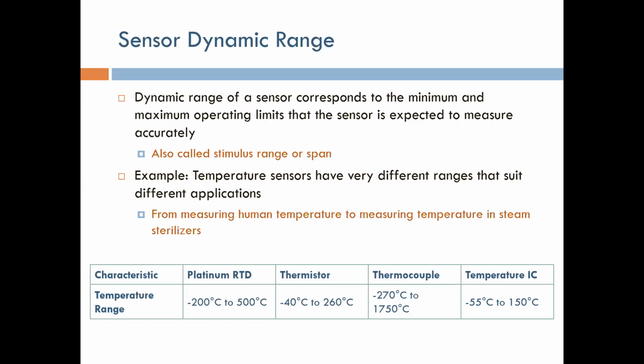The problem comes when you're trying to measure, for example, the temperature in a steam sterilizer. In a steam sterilizer, you might have really high temperatures. So you need a sensor that can handle very high temperature to be able to measure the steam temperature, and this can be in the hundreds of degrees centigrade.